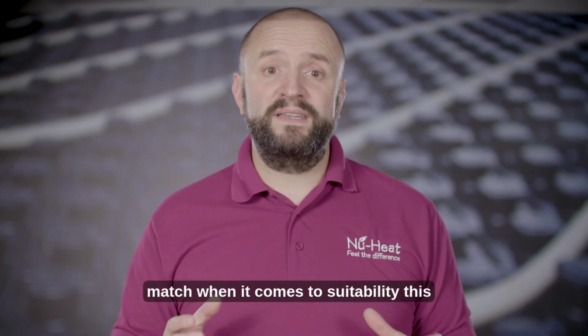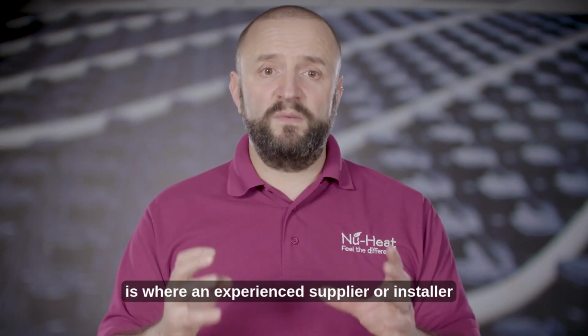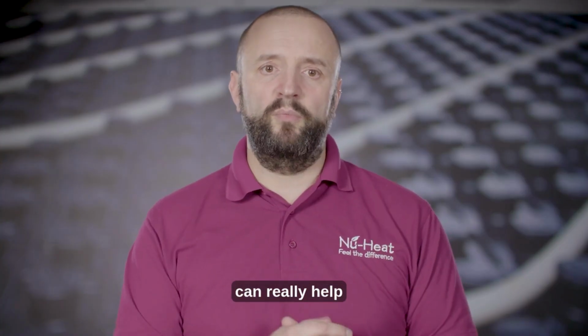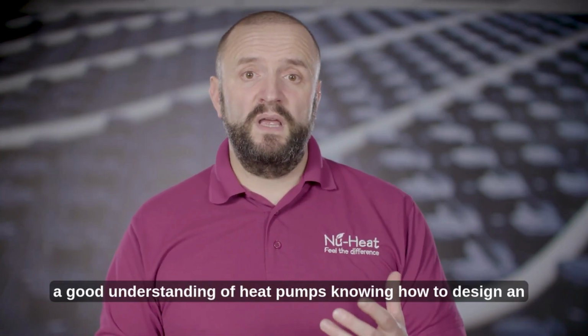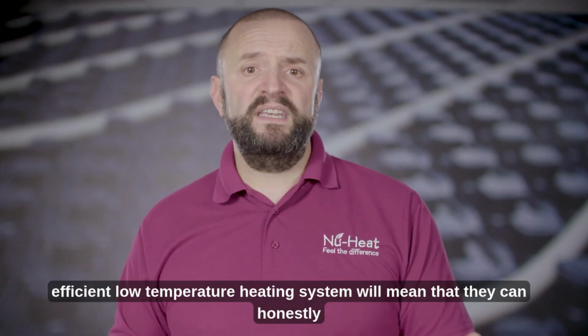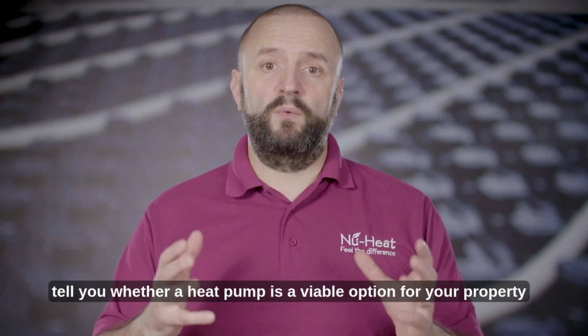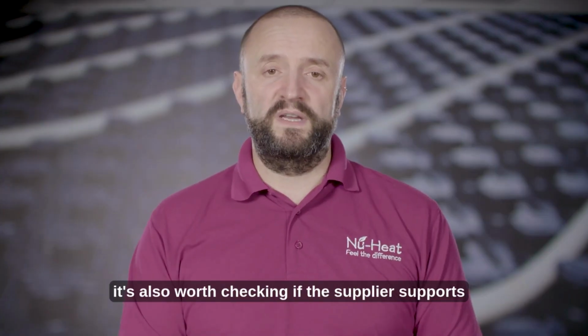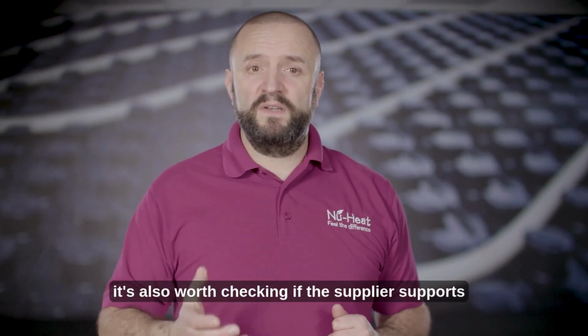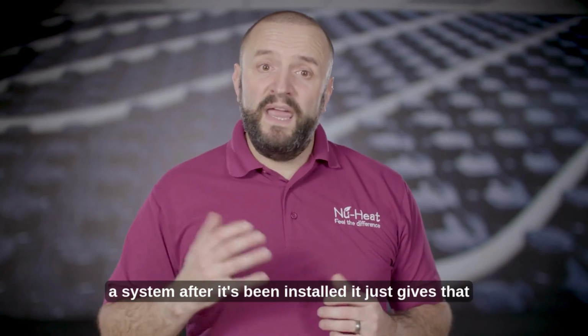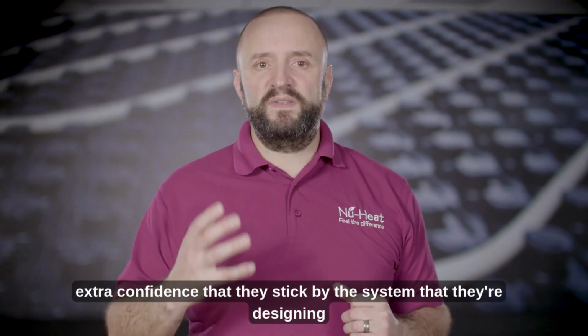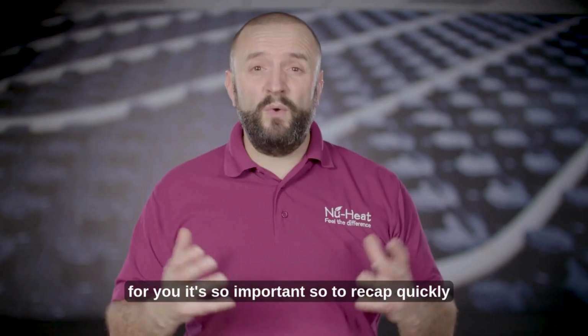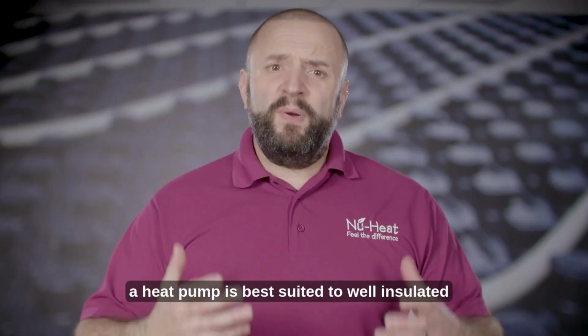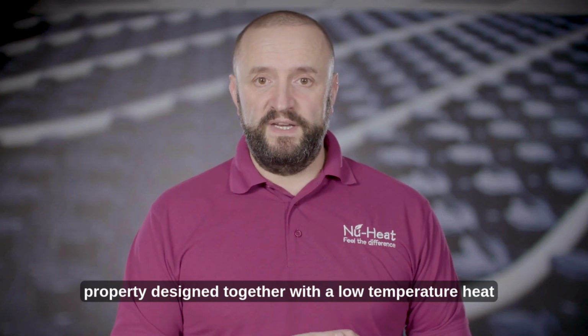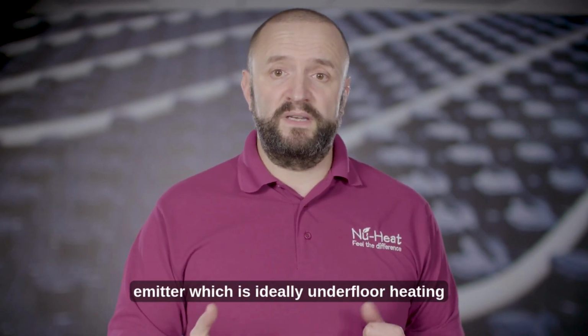When it comes to suitability, this is where an experienced supplier or installer can really help. A good understanding of heat pumps, knowing how to design an efficient low temperature heating system, will mean that they can honestly tell you whether a heat pump is a viable option for your property. It's also worth checking if the supplier supports a system after it's been installed. It just gives that extra confidence that they stick by the system that they're designing for you. It's so important. So to recap quickly, a heat pump is best suited to a well insulated property, designed together with a low temperature heat emitter, which is ideally underfloor heating.